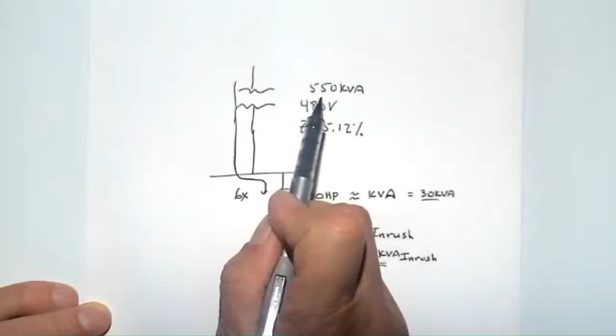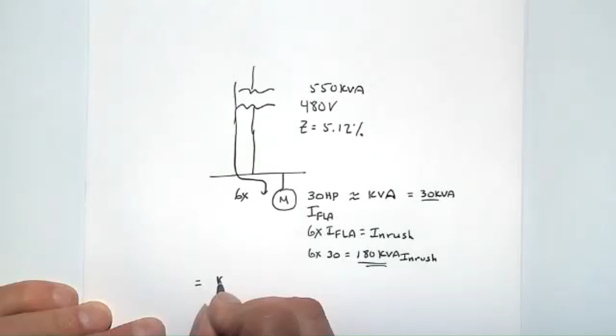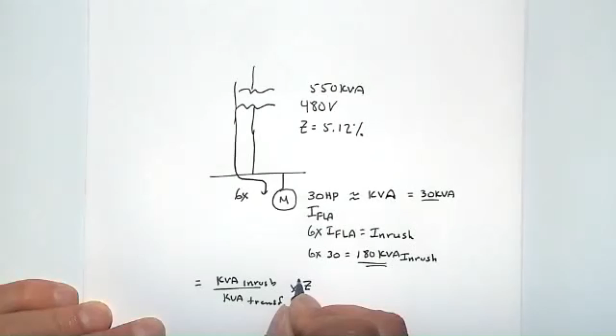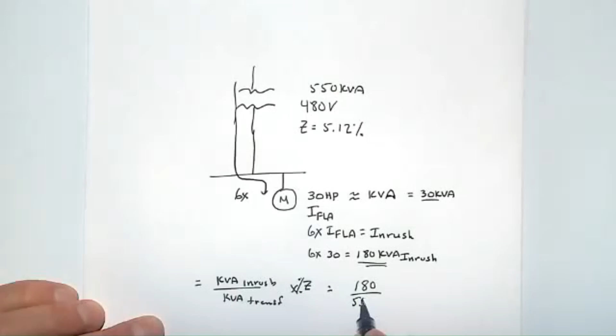So if we take that inrush kVA and look at the ratio of that inrush kVA versus this transformer size, we take kVA inrush divided by kVA of the transformer and multiply it by %Z. We get 180 divided by 550 times 5.12%, and that ends up being 1.67% voltage drop.